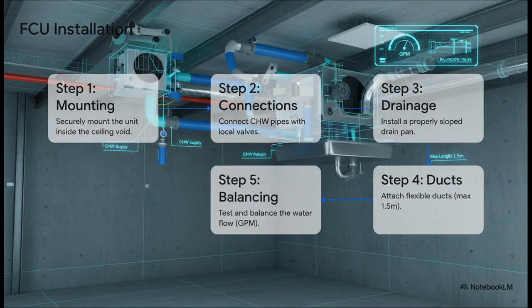Now for the smaller FCUs, the big challenge with these is that they're tucked away inside a crowded ceiling, so the installation has to be absolutely perfect from the get-go. After it's mounted, all those connections, the pipes, and especially that all-important slope drain pan have to be triple-checked, because once that ceiling is closed up, they are a real pain to get to. And notice step 4. There's a very specific rule that the flexible ducts can't be longer than 1.5 meters. Any longer than that, and you lose way too much air pressure from friction, basically starving the room of cool air. It's these tiny details that make or break the system.